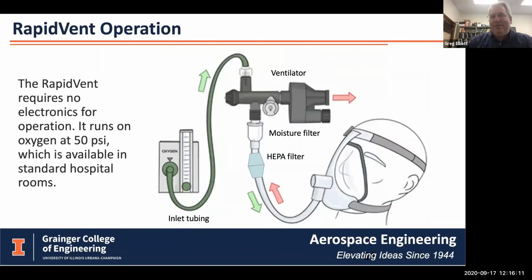Let me describe a little bit about what this RapidVent is. The RapidVent was designed so that we went over to the hospital and looked at the kind of oxygen supply they had, and designed it so that it could be incorporated into many of the rooms, not only the ICU rooms that had 50 PSI of oxygen available. Then there are some filters that they always want to put on. Most likely this would be used with an intubation tube, but it's shown here with a mask.